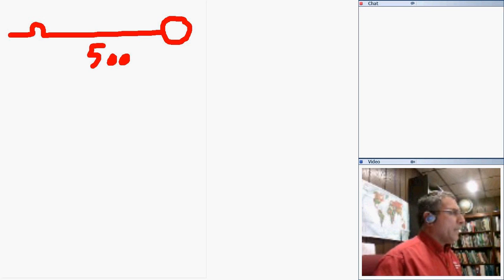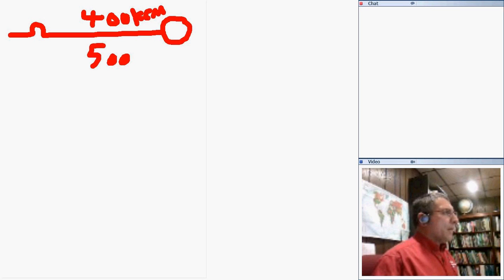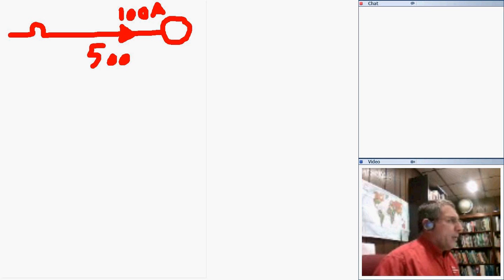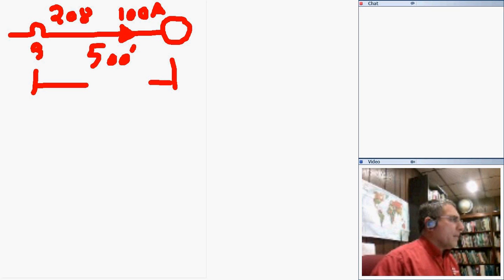Let's put it this way. Let me have those guys here and do a voltage drop calculation. The distance is 500 feet. Let's go size the conductors. Let's go to the table and find the amps. I have a 100 amp load, non-continuous. If I have to size a 100 amp load over a distance from here to here of 500 feet, and the voltage is 208 three-phase, my circuit needs the conductor sized based on these circumstances.